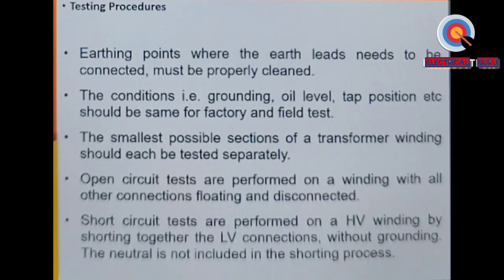The smallest possible section of a transformer winding should each be tested separately. Open circuit tests are performed on a winding with all other connections floating and disconnected. Short circuit tests are performed on a HV winding by shorting together the LV connections without grounding. The neutral is not included in the shorting process. So we check the open circuit impedance, we check short circuit impedance, and based on that we do some calculations.